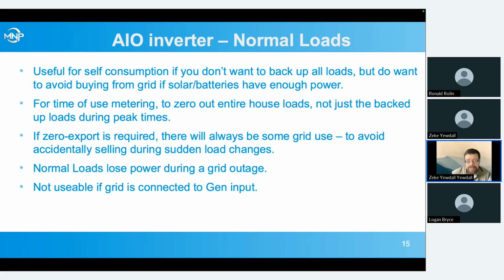If we have time of use metering, and during those peak times, we don't just want to avoid drawing power from the grid for our backed up loads. We would like to avoid drawing power from the grid for all the loads in the house, even the ones that are not important enough to be backed up, or maybe they're too large or too energy intensive. But we could zero them out during that peak time period. So that's use of the support normal loads.